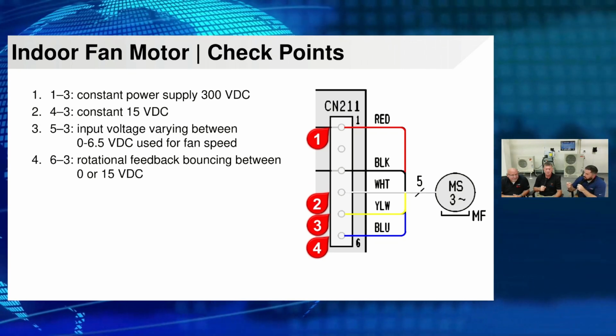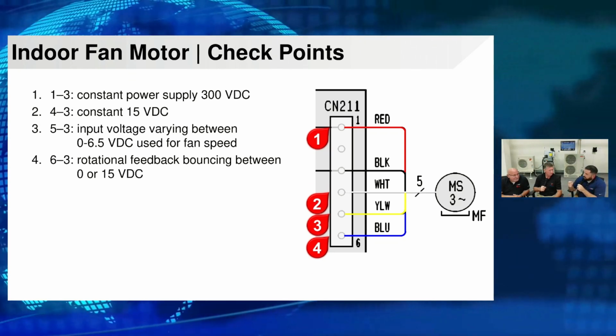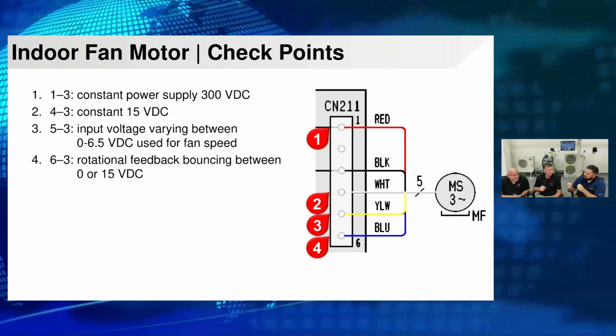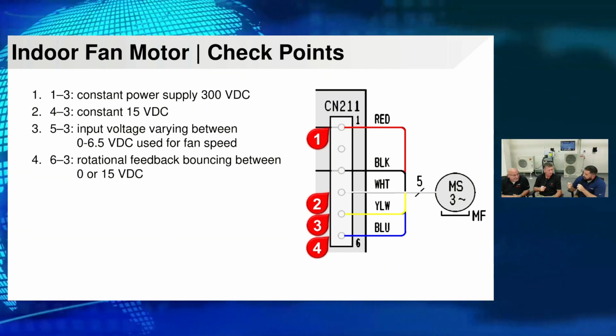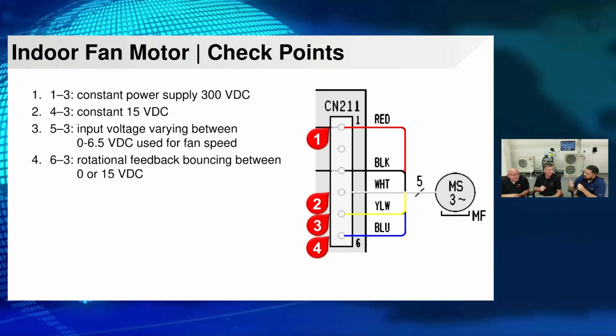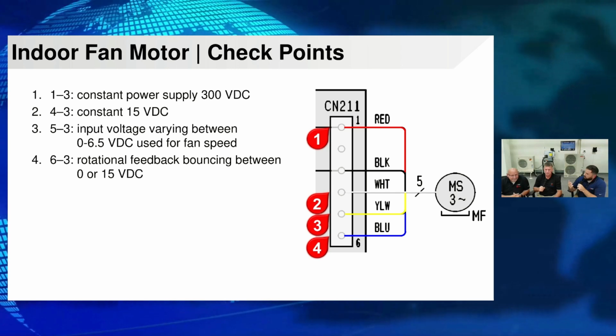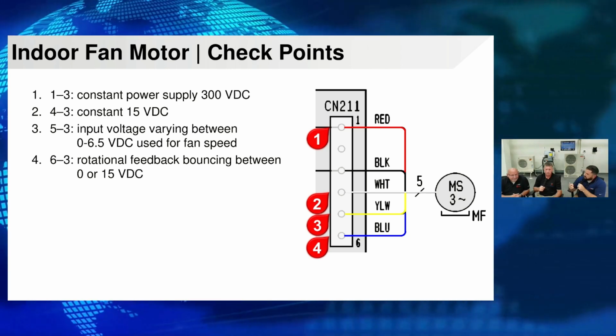So anytime we look at a motor connector from one of our residential units or indoor fan motors, all we have to do is find the gap - look for the one on its own. That's going to be your gap, and that's your power and common. Then it's always feedback in, speed control, feedback out.